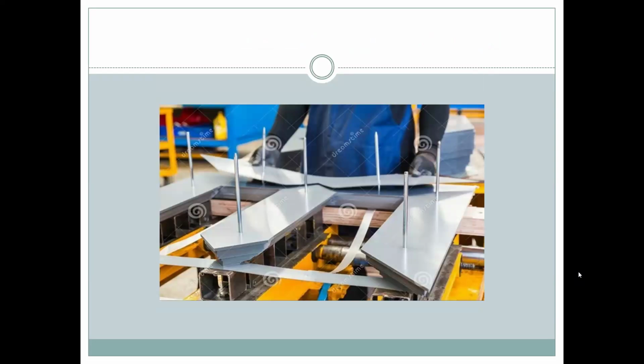Transformer is a product. You will see that delivery is a big problem when we ask for this transformer, because so much manual labor is involved. In motors, since I am from both industries, the motor rotor has now become mechanized. So the rotor rolls out with the machine. But for the transformer, this core building, simple core building, is 100% manual.